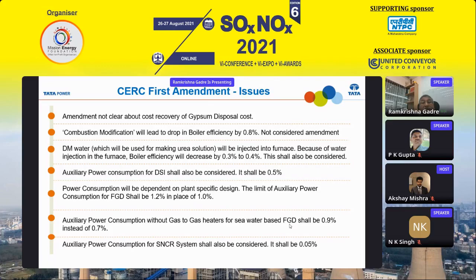For all plants, auxiliary power consumption has been given as 1%, but we feel there should have been a little more room for plants. Specific variation also needs to be taken into account, because in some plants where space is not available, gypsum handling or limestone handling, gypsum dewatering and all those systems are required to be installed far away from the scrubber area. In those cases, a lot of handling of gypsum and limestone to and fro happens, and the auxiliary power consumption may not be able to meet within 1%. So no allowance has been given for site-specific issues.